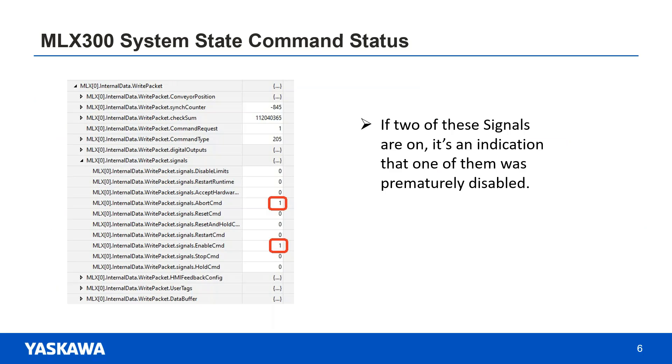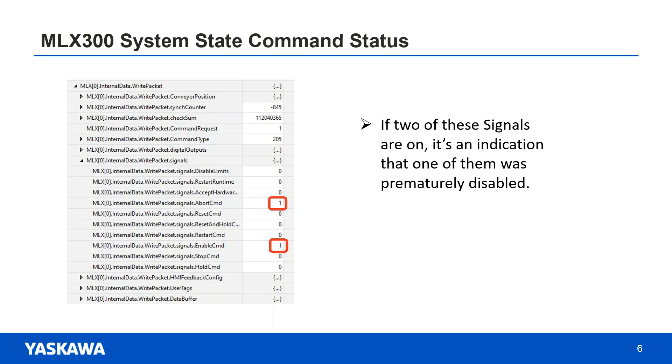There is a place in the MLX tag array to check the status of all of the system state commands. Under the MLX internal data write packet signals, the status of each system state command can be observed. If there are two on at the same time, that means there's an issue. This will give you some guidelines on which commands to investigate in the program to determine why both of these AOIs have been commanded at the same time.